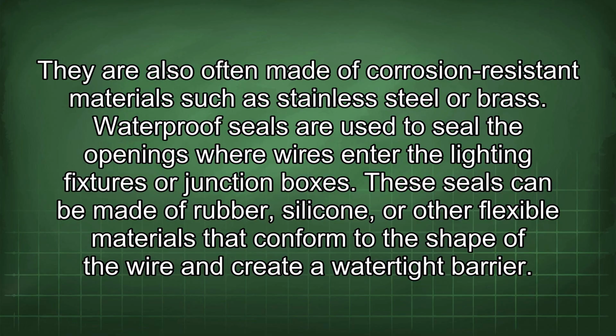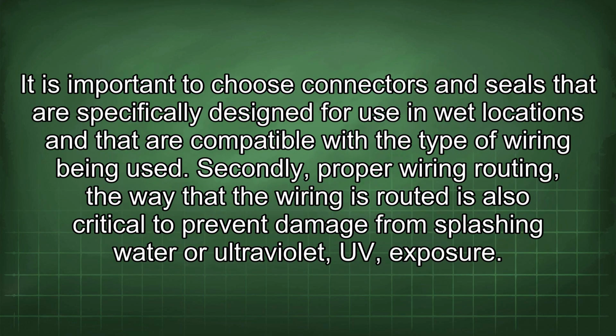Waterproof seals are used to seal the openings where wires enter the lighting fixtures or junction boxes. These seals can be made of rubber, silicone, or other flexible materials that conform to the shape of the wire and create a watertight barrier. It is important to choose connectors and seals that are specifically designed for use in wet locations and that are compatible with the type of wiring being used.